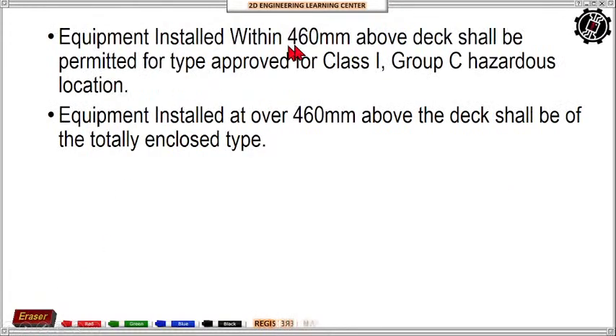So, equipment installed within 460 mm above the deck shall be permitted for type approved for Class 1, Group C hazardous location. No? So, yung lahat ng mga equipment natin, or lahat ng mga electrical equipment, which is within 460 mm above the deck, shall be permitted as long as yung approved niya is for Class 1 Group C hazardous location. No? So, itong Class 1, Group C hazardous location ay makikita doon sa special conditions, no? Kung ano yung ibig sabihin nito. So, this is all about yung may mga, there is a chance, no, that our equipment will ignite, no?